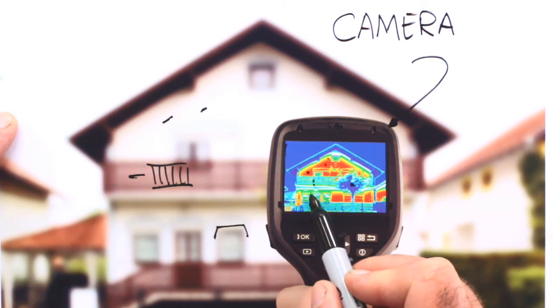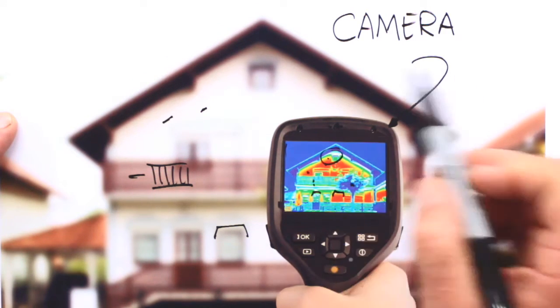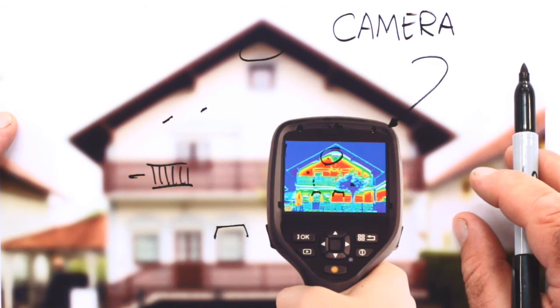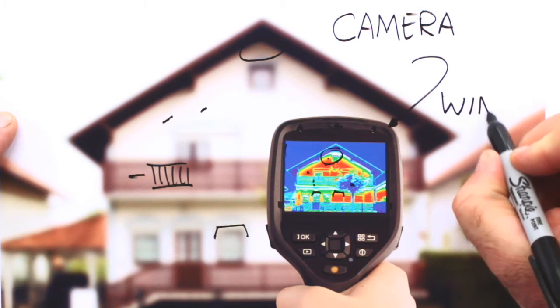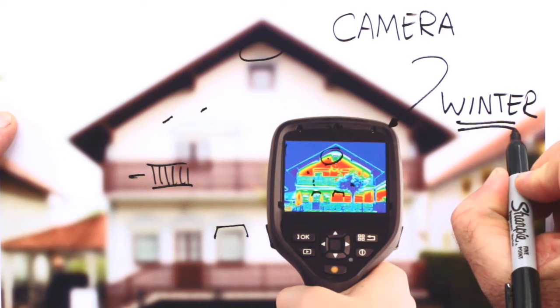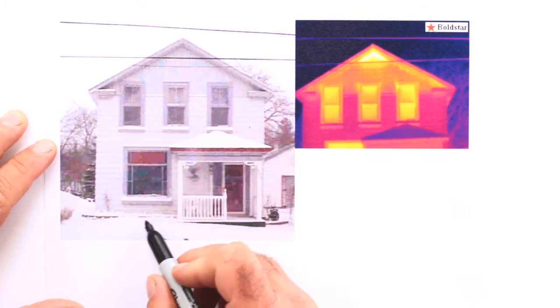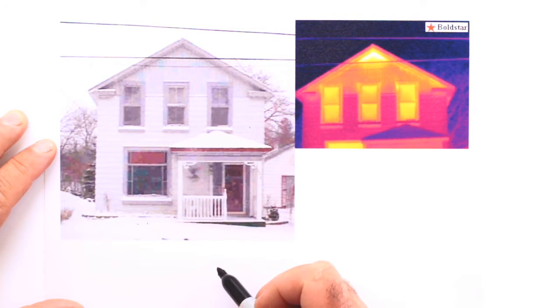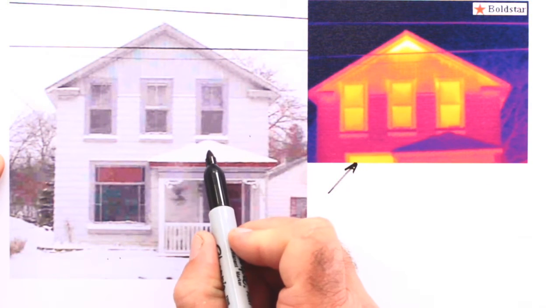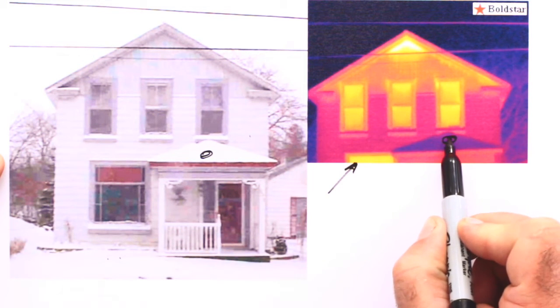In areas of the wall we start to get into brighter colors that show higher surface temperatures — you see that especially in windows, in the top area of windows. The brightest area of the image is up near the peak; that would be the hottest part of the house where the most heat loss is. You get the best results with this when you look at a home in winter, because that can really show heat loss. This is a typical Canadian home on a typical Canadian winter day.